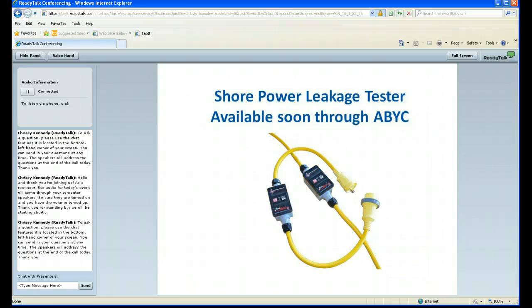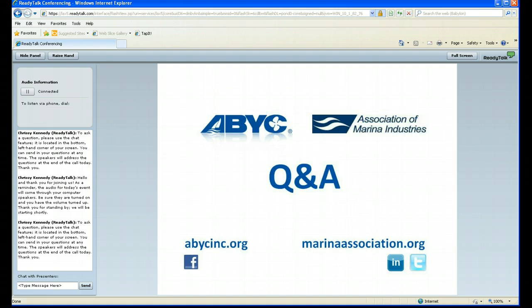Also, coming up in the next month or so, we expect to have available for purchase a low-cost way to determine whether a boat is emitting any leakage current onto the dock. If you look at the picture on the screen, this is simply a 30 amp pigtail with the same technology that is used in the boat ELCI. The idea is plugging in every boat every year and making sure that all the boats at your marina are not leaking any current into the water. We had one question in the chat room, and this is a very easy way to determine it. There's a light as well as a buzzer. This particular model does have the ELCI breaker in it, so it will cut off the power. We're also looking at one that just has a visual or audible indication so that you can do some fundamental troubleshooting to try to figure out what circuit on board the boat is having an issue. So that's something that ABYC is working on now.